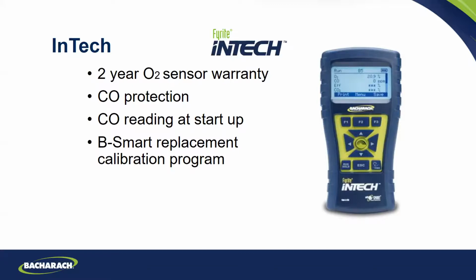If this ever sees 1200 - say one of your employees sticks this in the tailpipe of a truck and it sees 1200 - the pump shuts off. Or if your processor you're working in sees 1200, the pump shuts off, and it just saves that CO sensor. It's good for the CO sensor to protect it from seeing high concentrations anyway, because high concentrations deteriorate the life.